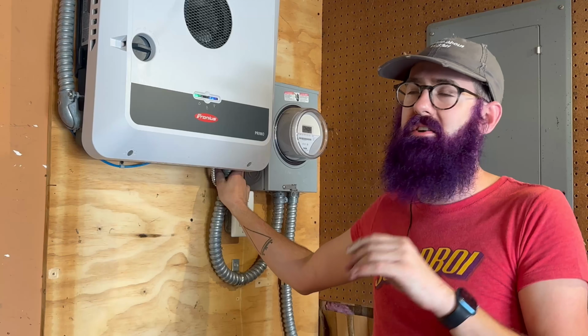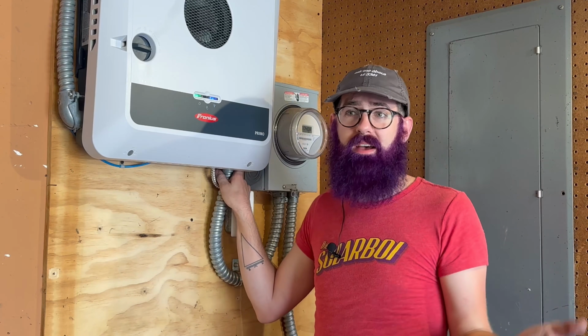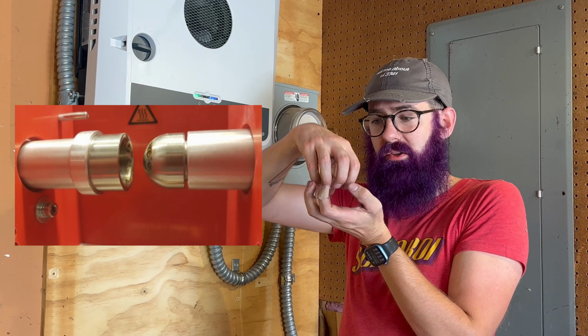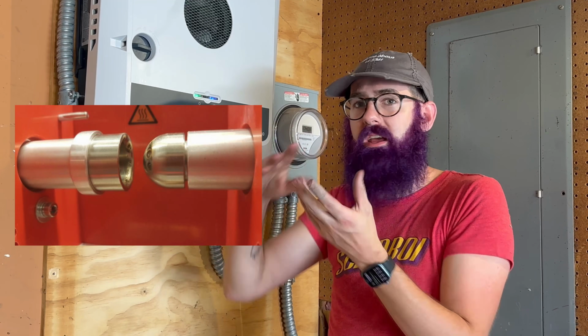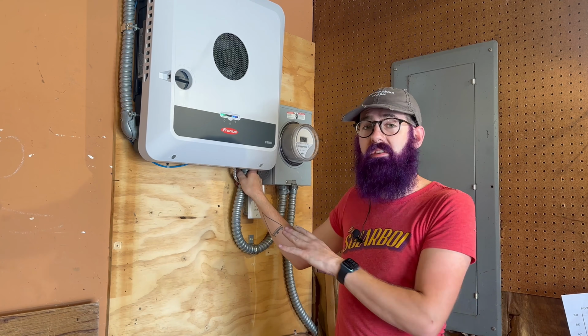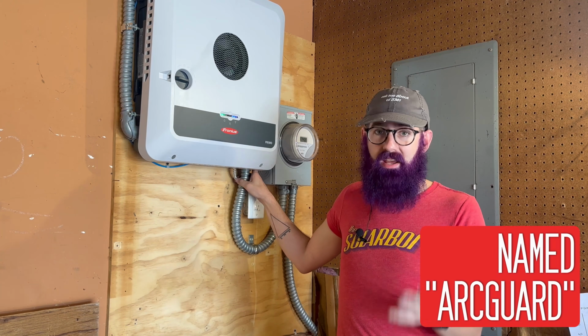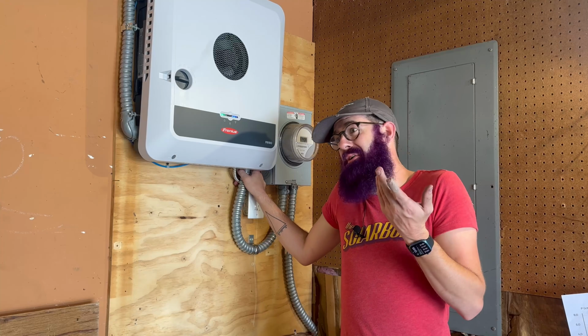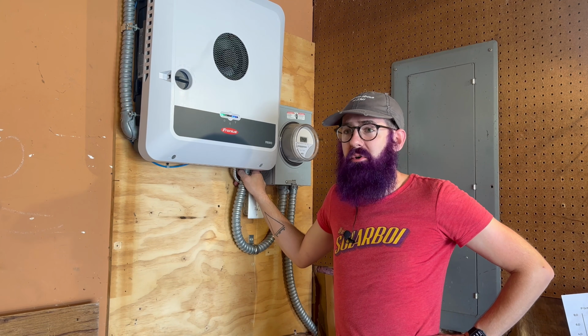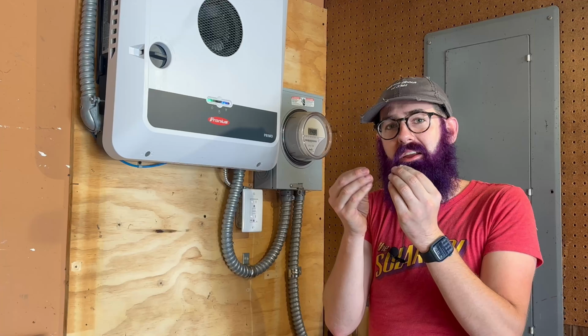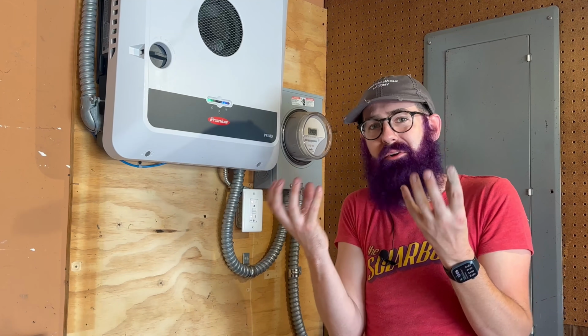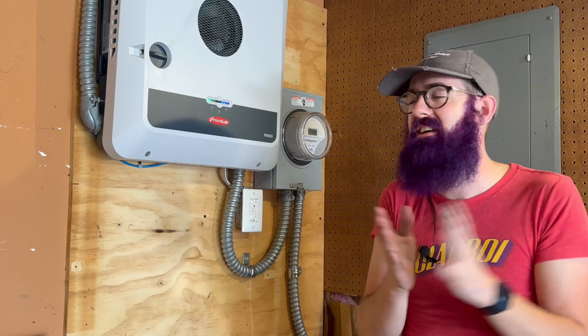Arc fault detection has gone through a lot of evolution over the last 10 to 15 years. We've gone from simulating an arc fault with steel wool slowly pulled apart to capture that signature, to using more of a ring and ball method where you slowly separate them until you get some arcing, which is more representative. Fronius says their algorithm, built from welding data, both passes the ring and ball test and is as accurate as humanly possible. It's just cool. I find it great that welding and solar come together to form a solution to a problem the solar industry has had for 10 to 15 years. It makes me happy.